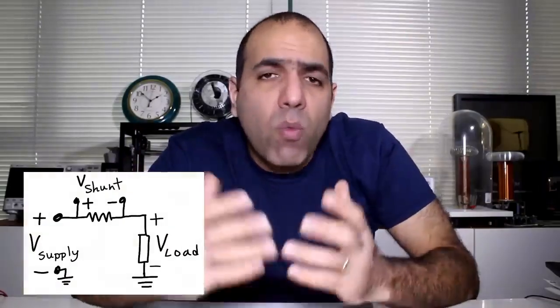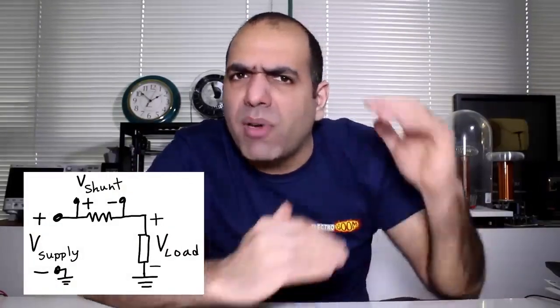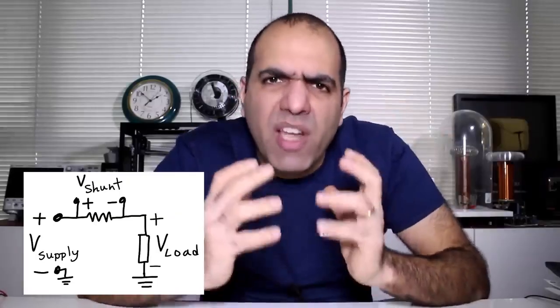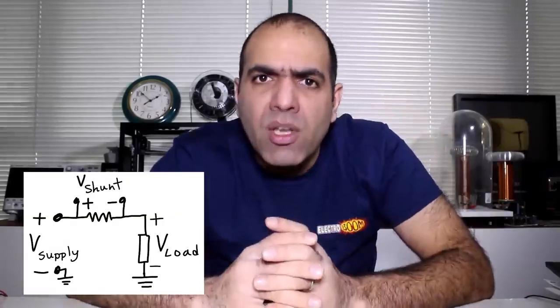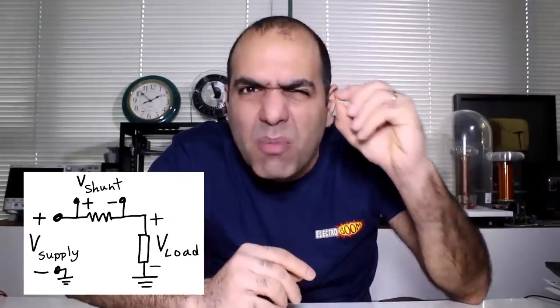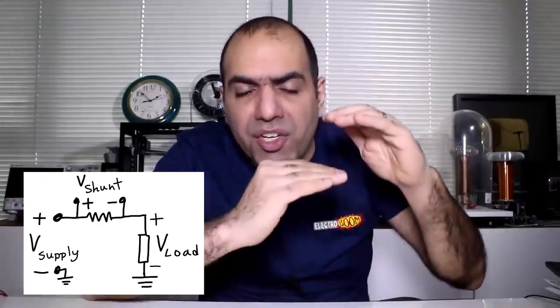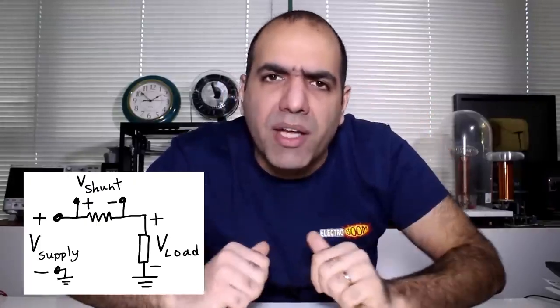Using a shunt resistor, you are generating a voltage drop that's not very desirable. Why? Because you are dropping your supply voltage level by that much, which will affect the current running through the load. But if you keep that voltage drop small, or compensate for it by increasing the supply voltage, then you're fine.